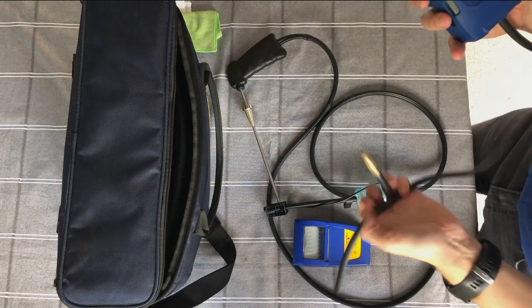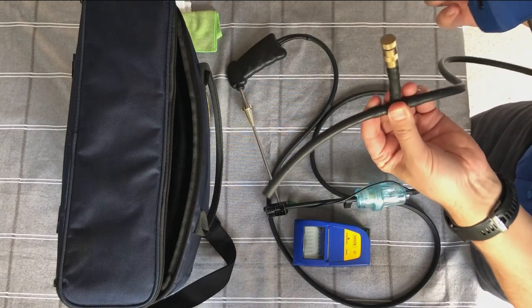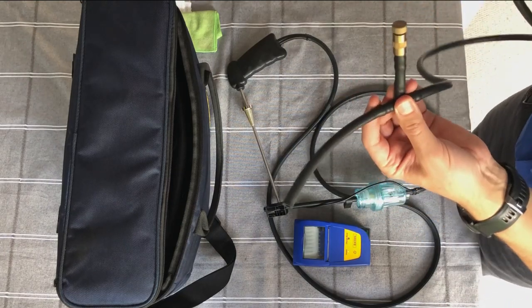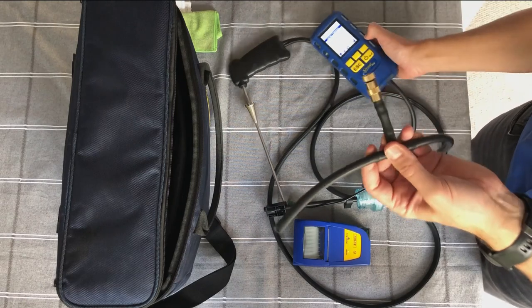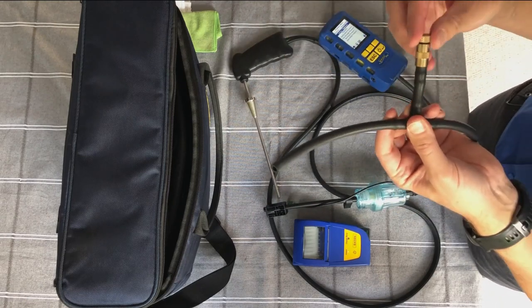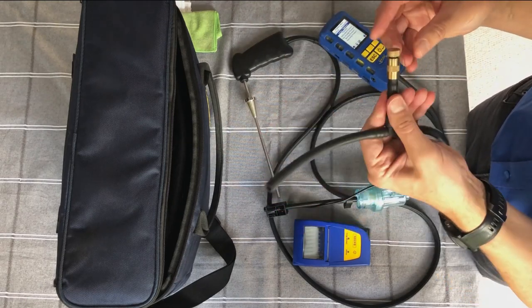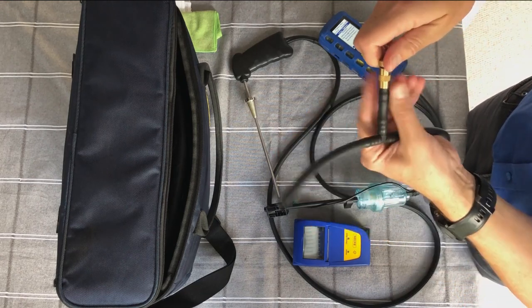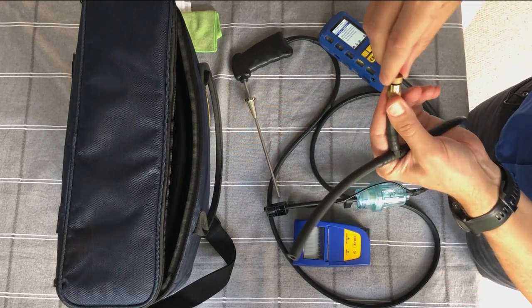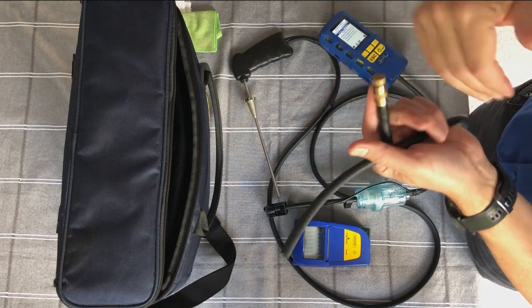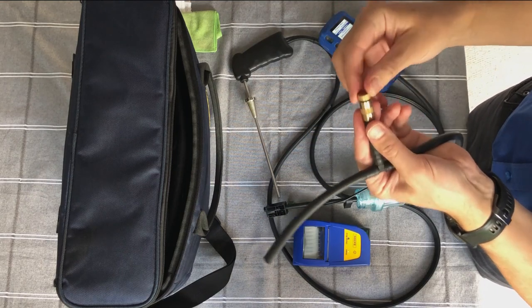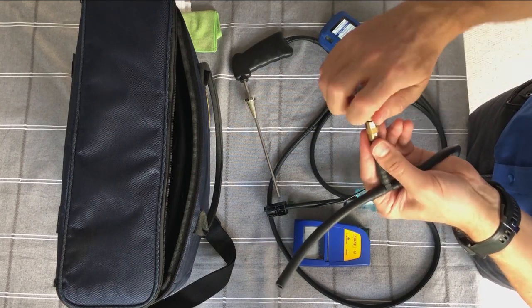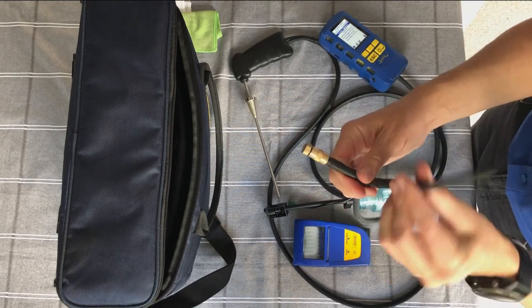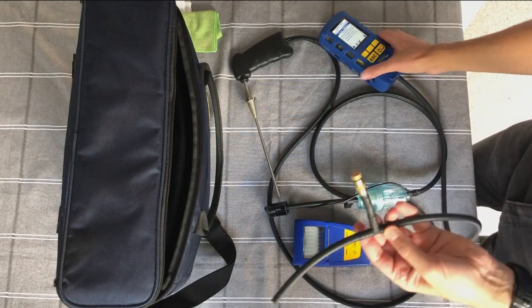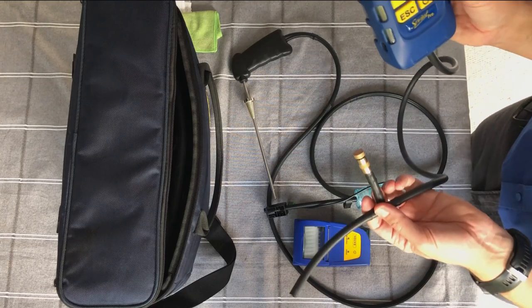Okay, so for those of you not sure what this is, it's a pressure relief valve. What you would do is go to your meter, open it up, and get the 23 millibar, whatever the standing pressure is at the meter. Then you can open this little bleed valve here to bleed it down to the 20 or 10 millibar starting pressure that you want to get to. So yeah, really handy little tool, very useful when you're doing your let-by tightness tests.